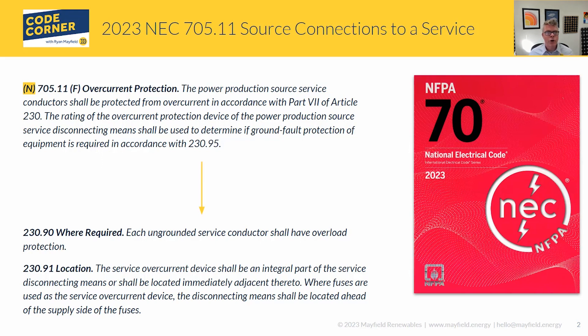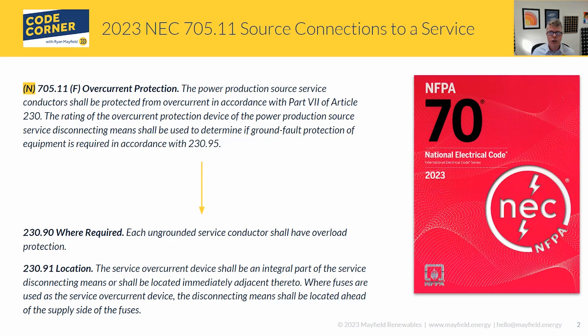When you read 230.90, the very first thing it says is each ungrounded service conductor shall have overload protection. Going to Article 100, the definition of overload covers equipment or a conductor operating in excess of its normal rating or ampacity, which when it persists could damage the conductor or cause dangerous overheating. The definition also clarifies that a fault such as a short circuit or ground fault is not an overload.